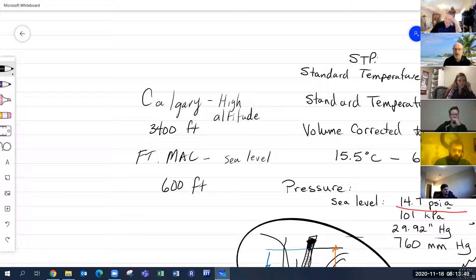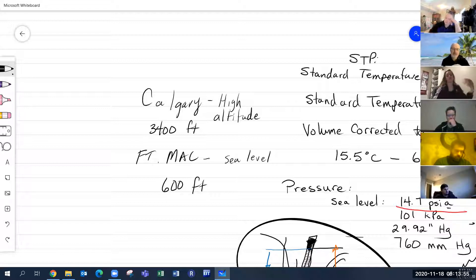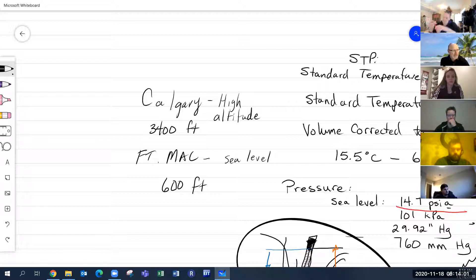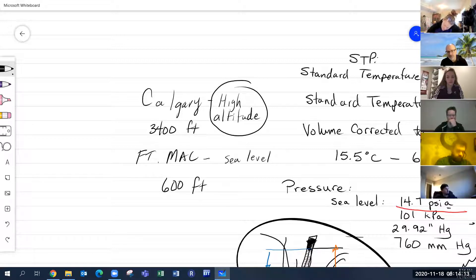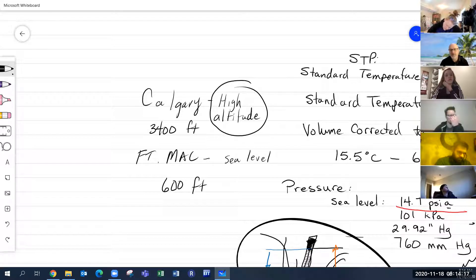If you live in a house with a furnace or a hot water tank, it should be rated at high altitude. It has to be de-rated — given a lesser input value in BTUs for high altitudes.